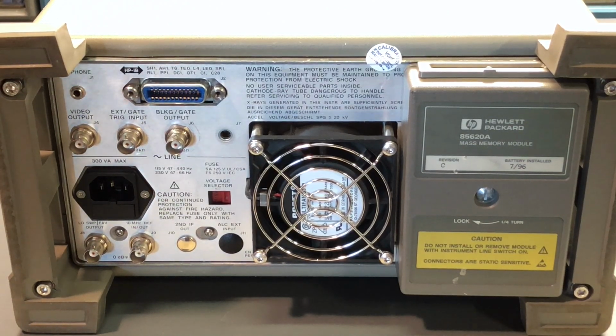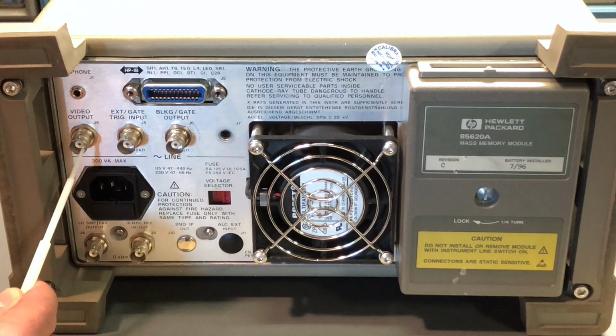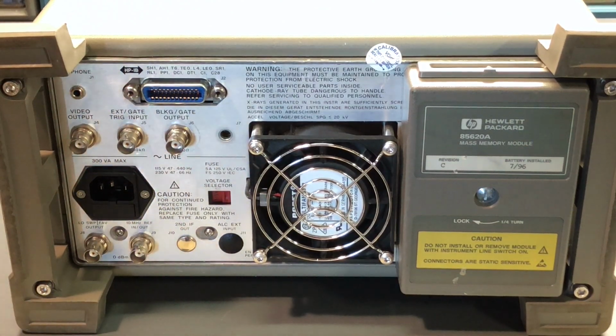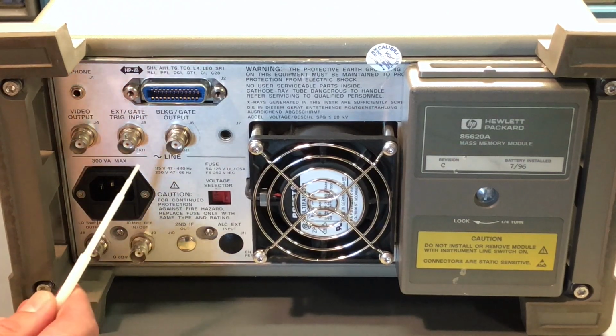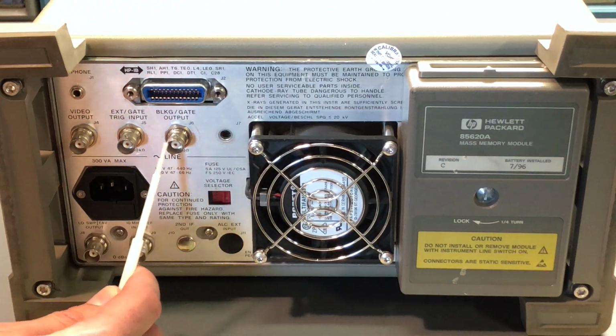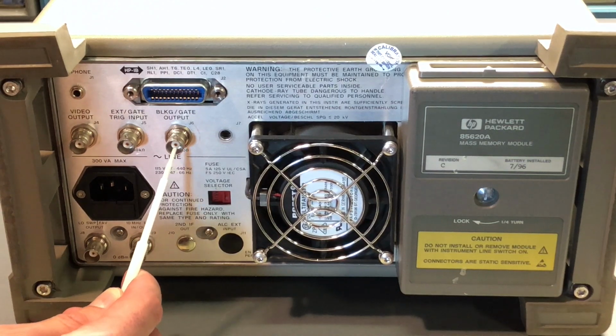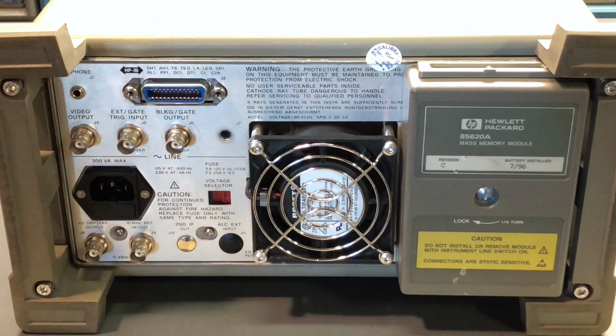Now right here, this video output is not a video like you would have going to, say, a television set or something like that. That video output is related to the vertical deflection of the trace, and it's a variable voltage that comes out of there. External and gate trigger input. Right here is a blanking and gate output. So this is related to synchronizing with external instruments, and also like a pen lift if you have an external plotter. Down here, this LO sweep, local oscillator sweep output. This is related to external tracking generator, and the function and what this does is related to some controls that are activated through soft menus on the front panel.